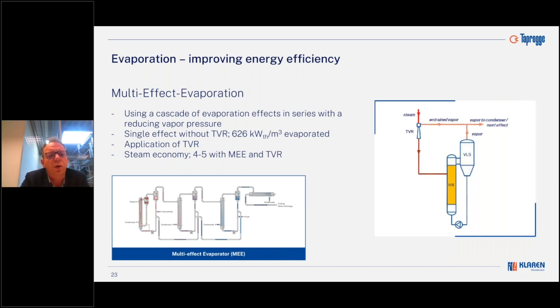Because one thing that you can do is, once you have evaporated the water, use this same vapor to condense again, and at the same time evaporate the second batch of water. So that's the cascade of evaporation effects in series, where you make use of a reducing vapor pressure such that, in sequence, you can use the vapor to condense, evaporate again, condense, and that then in X effects. And then you can improve what they also sometimes call the steam economy, with already a huge factor. So how many kg of water can you evaporate with 1 kg of steam, and you can reach numbers of 4 to 5. So then a number of 630 would already be reduced to something like 120, 130 kilowatt thermal energy that you require.